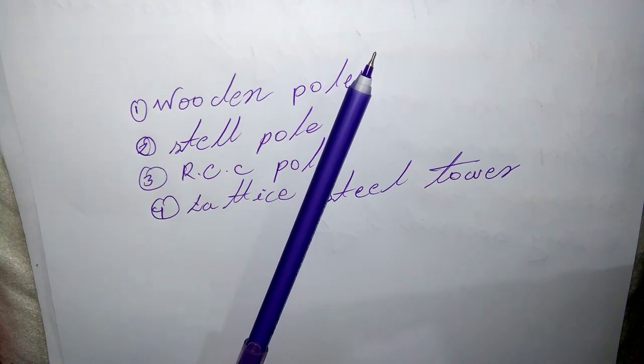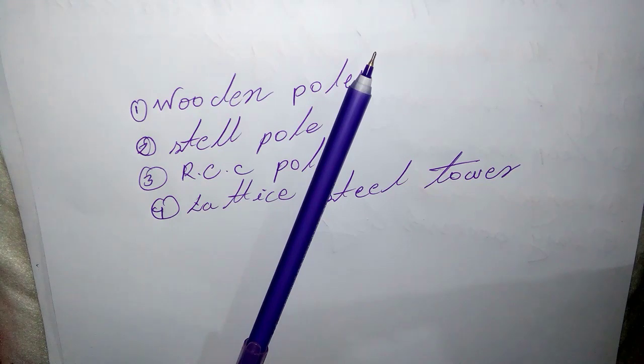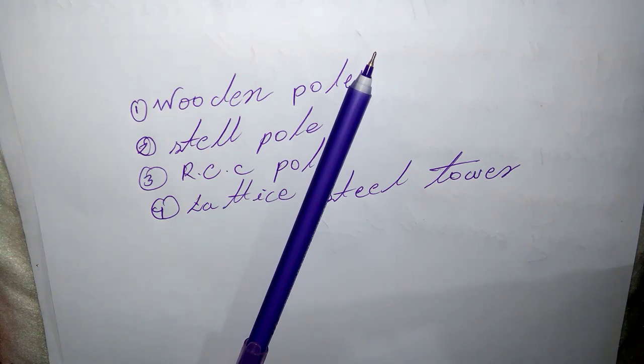The main objections of wooden supports are: tendency to rot below the ground level, shorter life of 20 to 25 years, cannot be used for high voltage above 20 kV, and less mechanical strength.